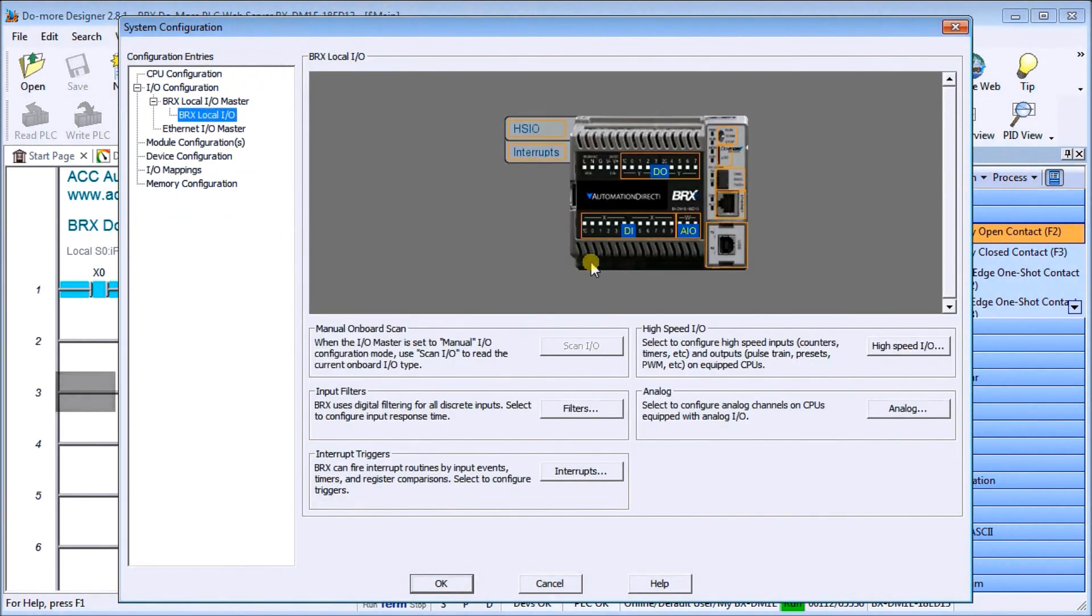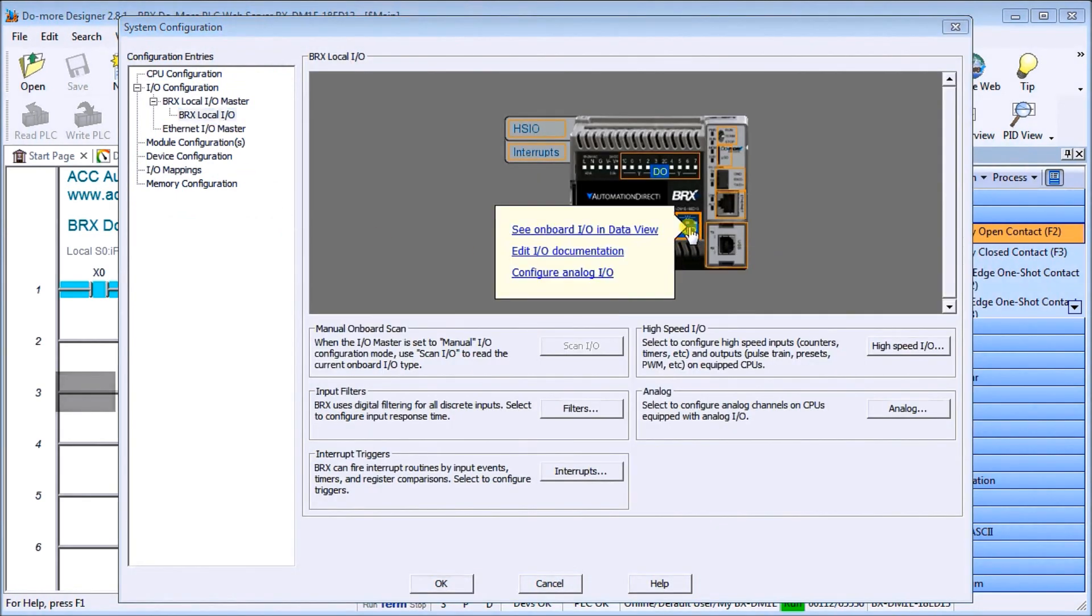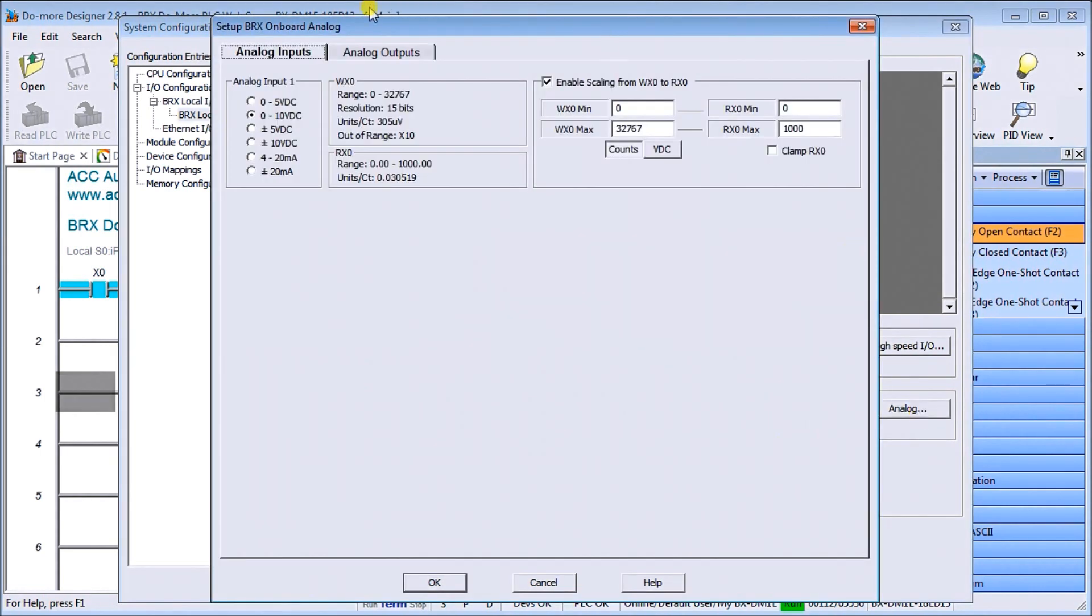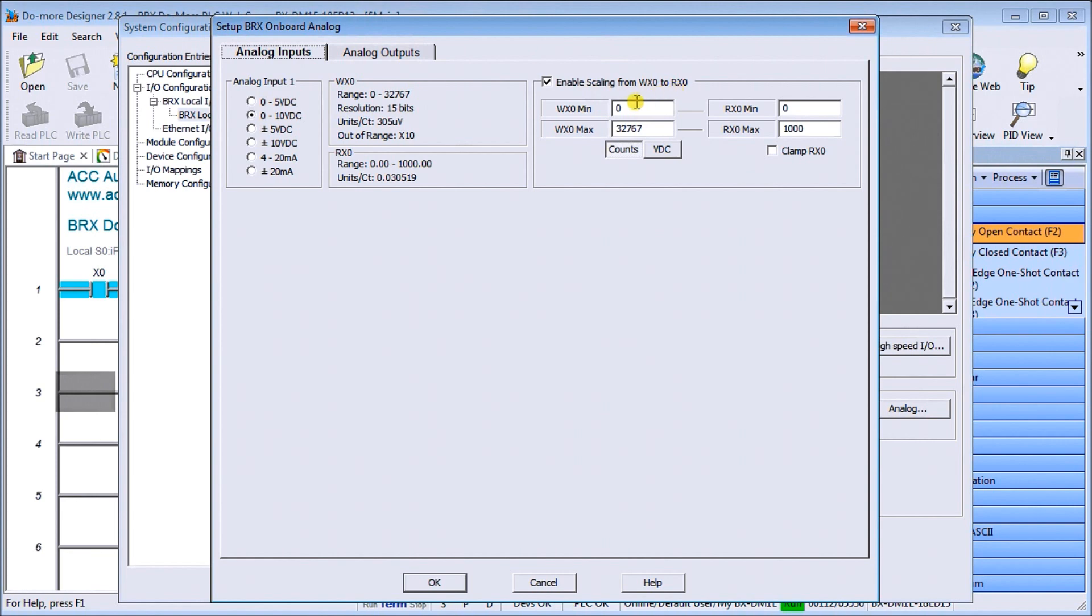Looking back at our system configuration we'll go to the BRX local IO, look at analog inputs and outputs. In our case here we're going to use our voltage input tester that we made from a 9 volt battery and a potentiometer, and we're going to feed that into our input signal which is 0 to 10 volt DC. We're going to enable the scaling so WX0 to RX0, going from 0 to 32,767 to 0 to 1000 representing like a percentage or voltage.